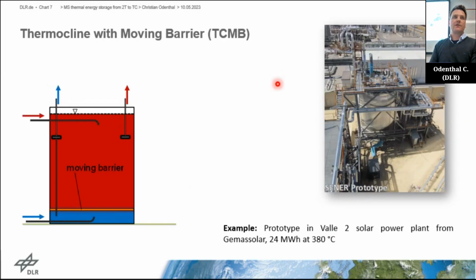The first one is the thermocline with a moving barrier. So what you do here is basically you add in a floating insulated layer, which must have a density which is a bit lower than the cold salt. So it has to float on cold salt without sinking, but it has to be a bit heavier than the hot salt, so that it sinks down in hot salt. And then you have a physical separation layer between the hot and the cold salt. And during operation, that barrier needs to move upwards and downwards, obviously. So that's also something you have to bear in mind.